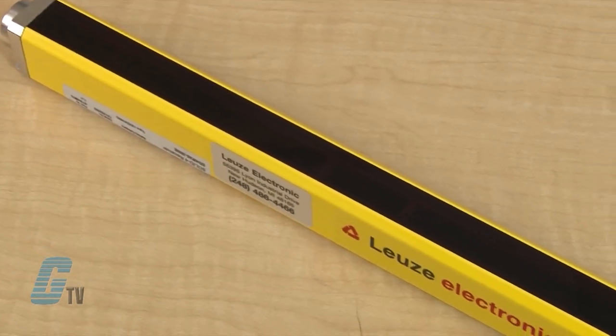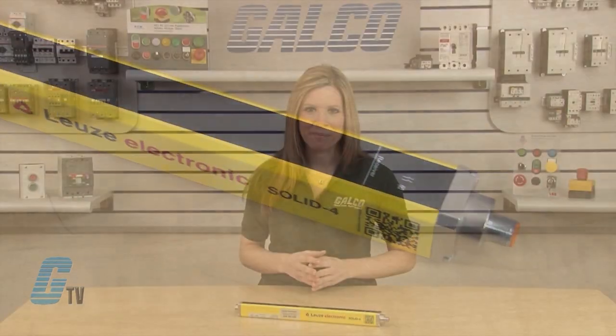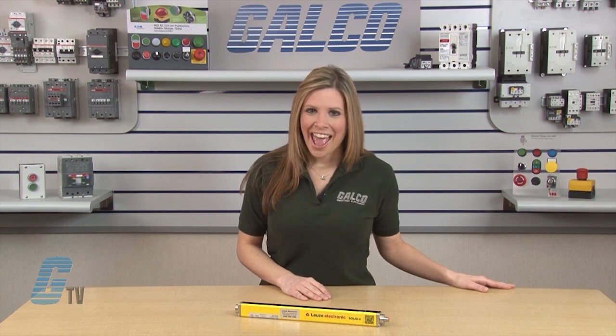Leuze's Solid-4 Series comes with an automatic start and restart function and an LED display. With a supply voltage of 24 volts DC, this model has a resolution of 30 millimeters, a protection field of 300 millimeters, and operates with a 0.5 to 9 meter range with a response time of 6 to 16 milliseconds.